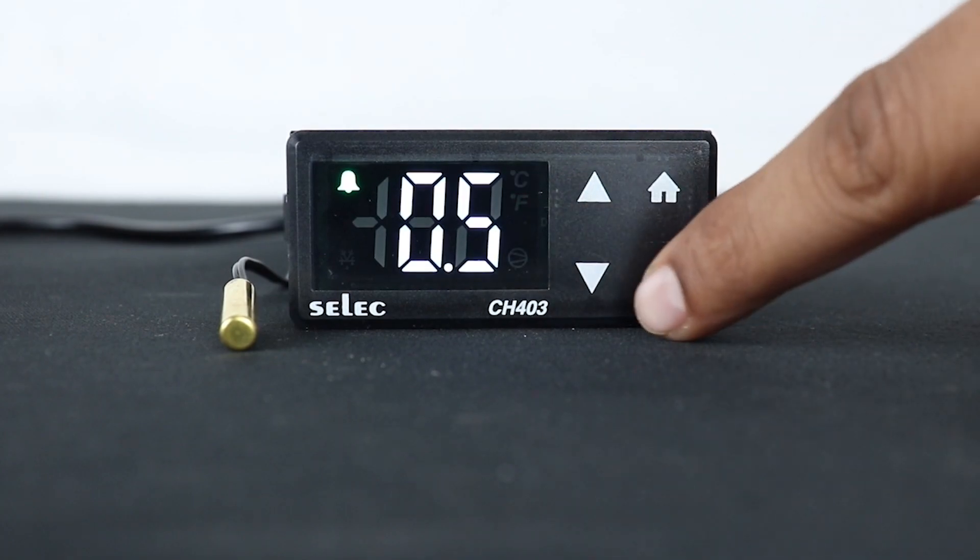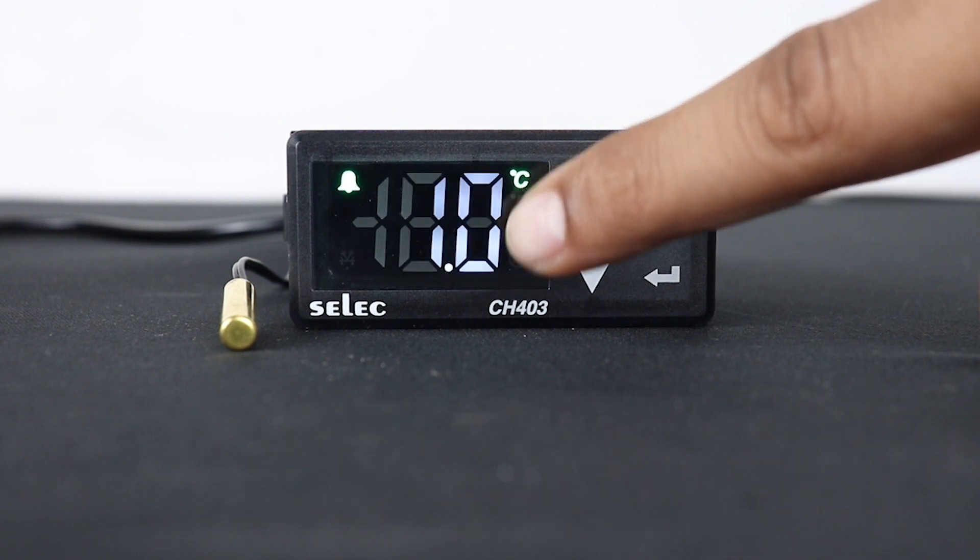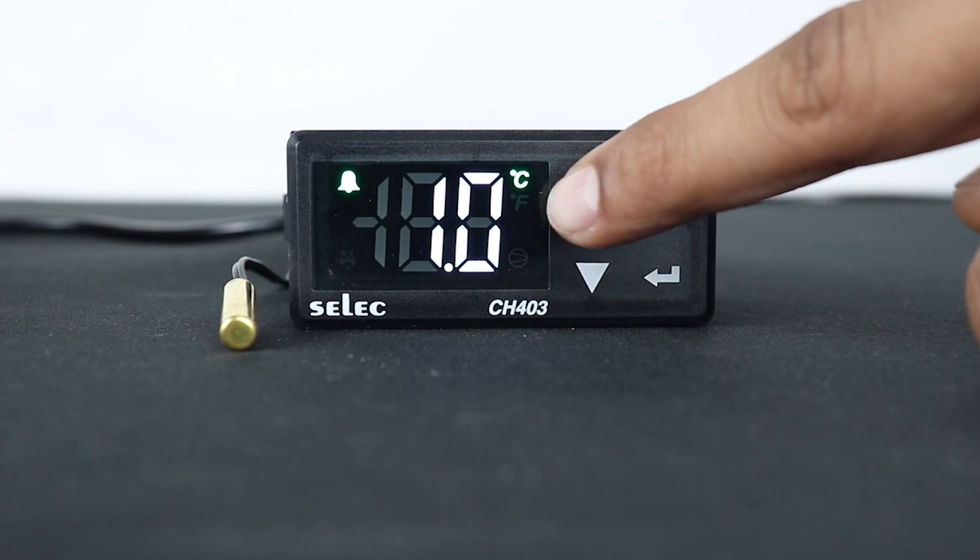P4 implies hysteresis parameter which is used to prevent frequent on-off switching of the relay around the predefined set point. Hysteresis parameter is very useful to increase compressor's life.